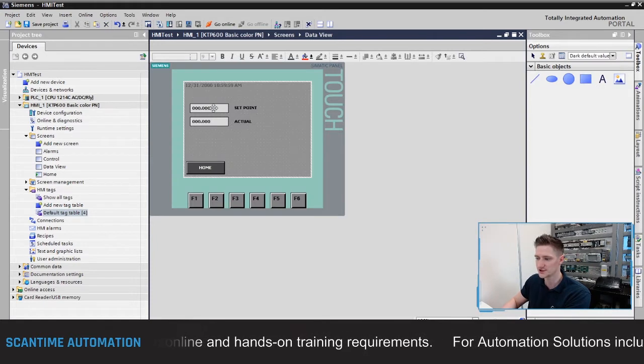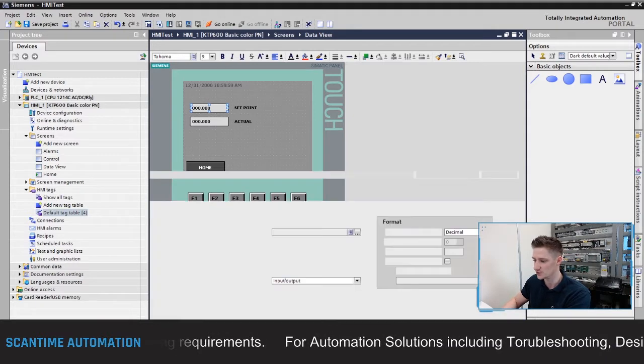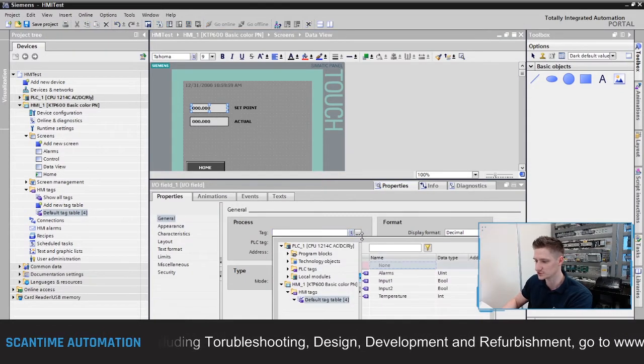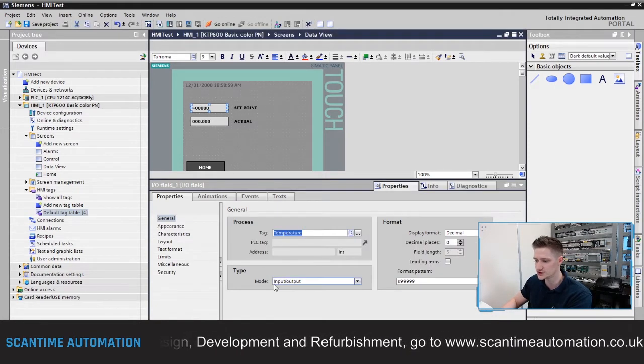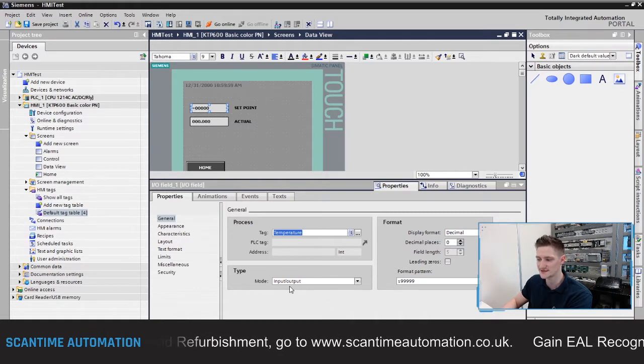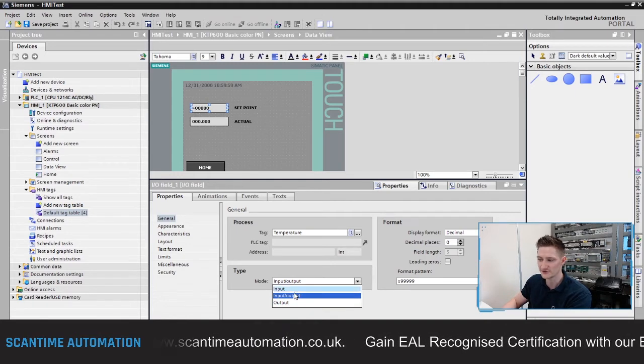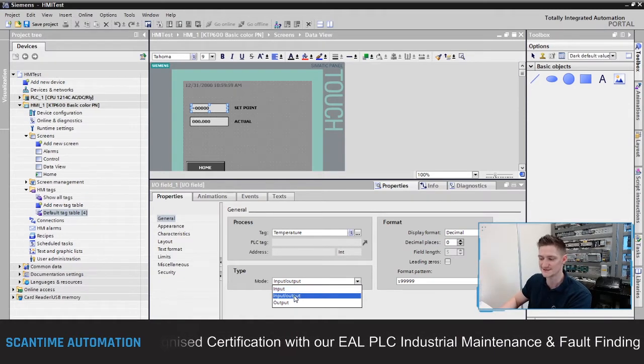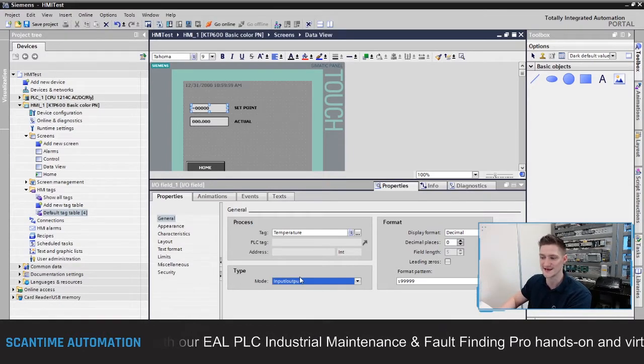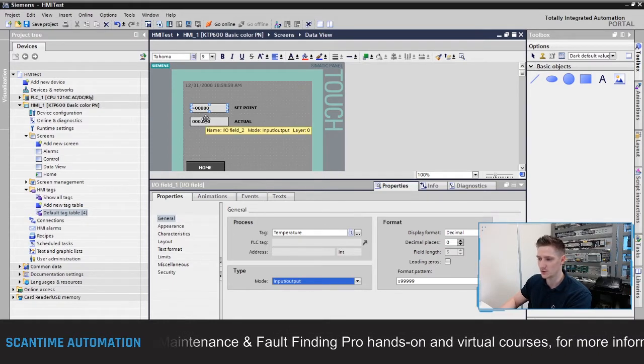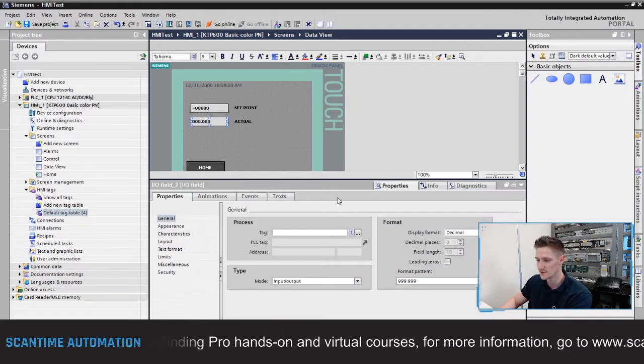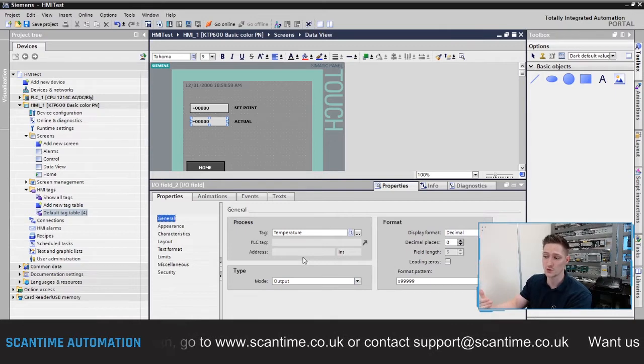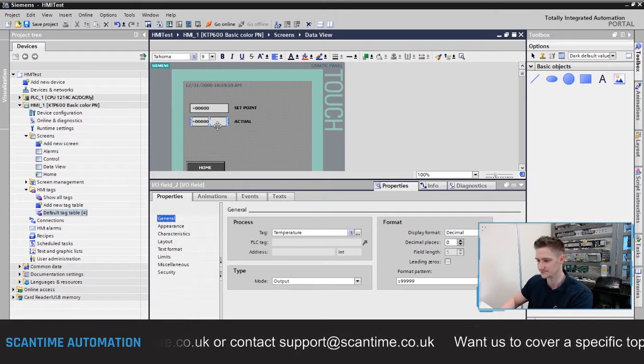Going back to Data View, I can set up these IO fields to read our temperature. In Properties under General, it asks which tag to assign — I'll click the three dots and select 'temperature'. You'll notice the mode is set to Input/Output, but you can change it to input only or output only. The Set Point field will stay as Input/Output, allowing the operator to type in a value. For the Actual field, I'll change the mode to Output only — this won't allow changing any value, it's purely for display.